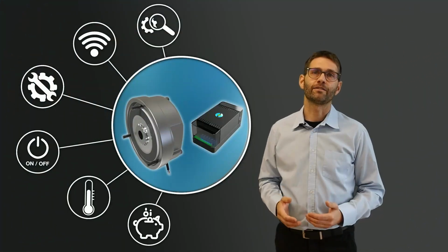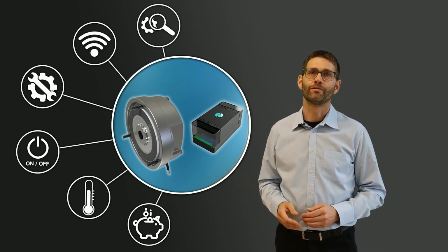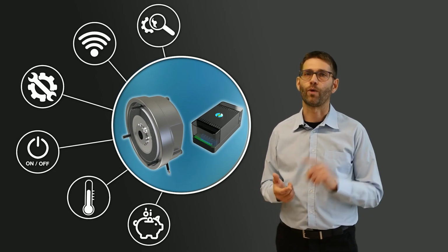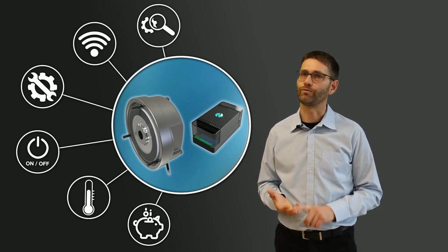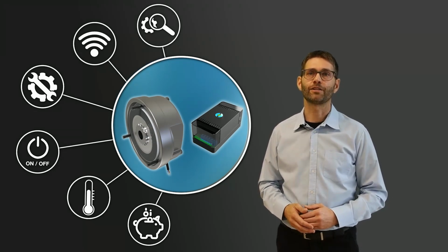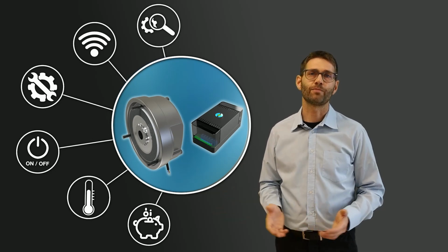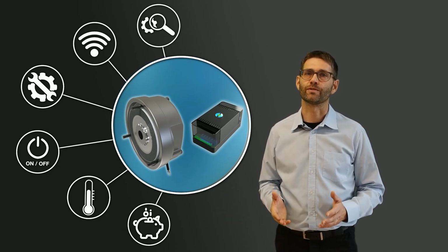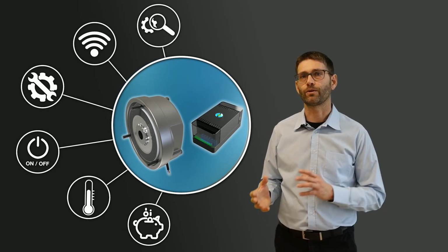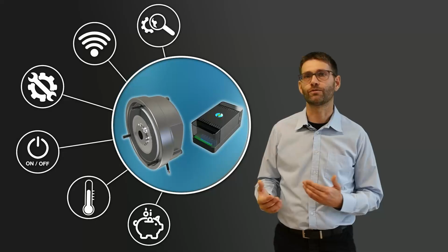In an extended version, the ROBA-brake-checker module is equipped with an additional board with a customer-specific interface, such as optical, wireless LAN, IO-Link, Profibus, and so on. Via this interface, the module can provide data on switching time, current, voltage, resistance, and power. This also makes it possible to evaluate sequences. Conspicuous features in the process can be quickly recognized, and thus conclusions can be drawn from complex interrelationships.